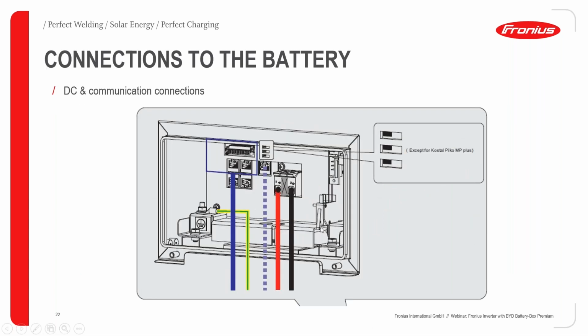This is the little micro switch, just here, and it gets pushed in when you push the side panel back on. Here's your earth clamp, and here you've got various connection points for communication, either via RJ45 or via a terminal block - we'll cover that in a minute. You've also got dip switches for your 120 ohm resistor, and of course your DC cables here too.